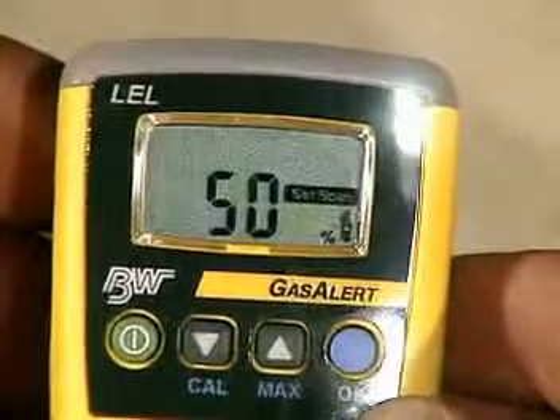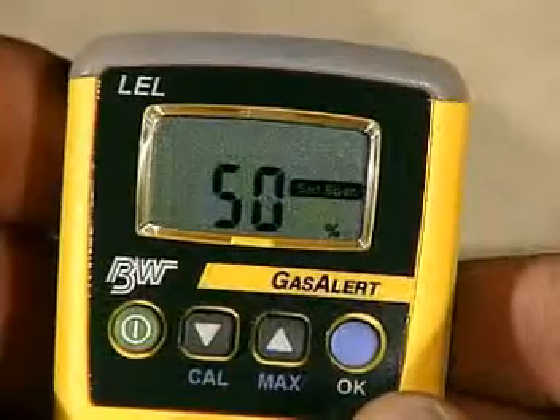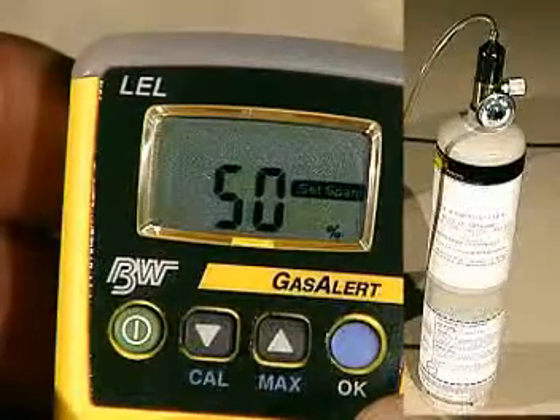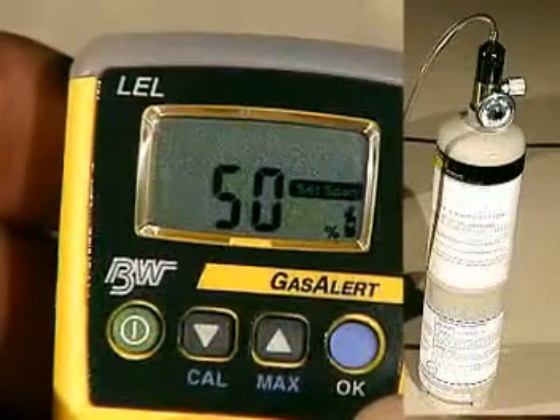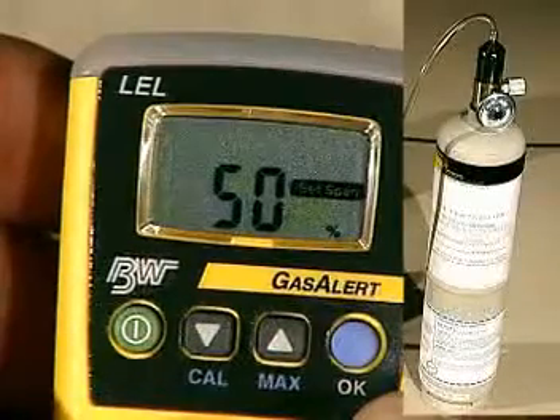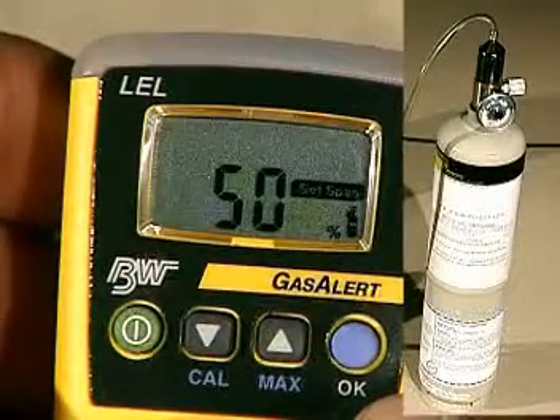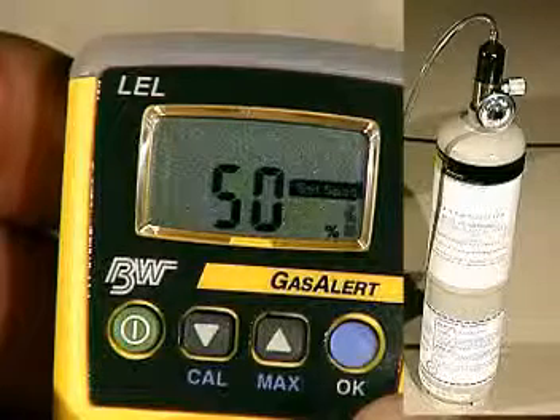Next, the flashing gas cylinder appears, prompting you to apply gas. Place the test cap over the sensor and apply gas. The audible alarm beeps 3 times to advise that span has been successfully completed.